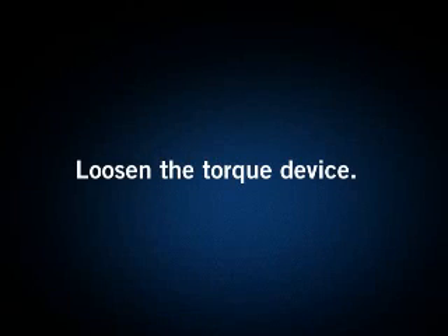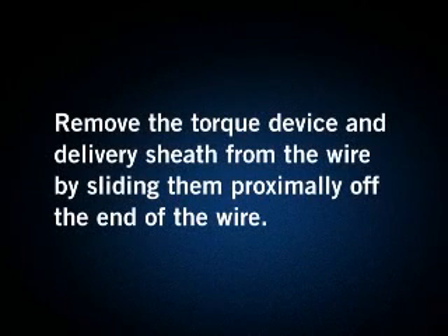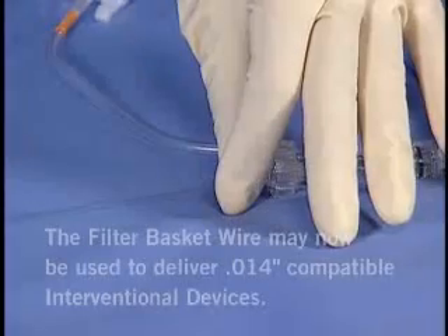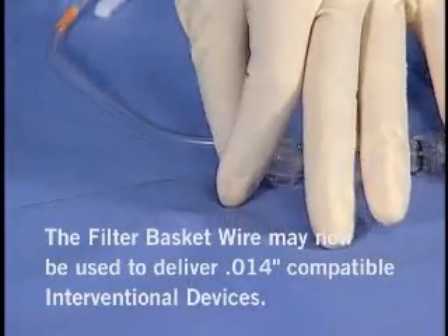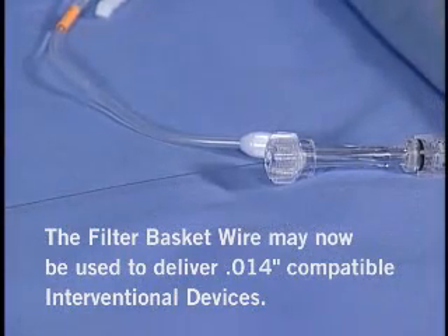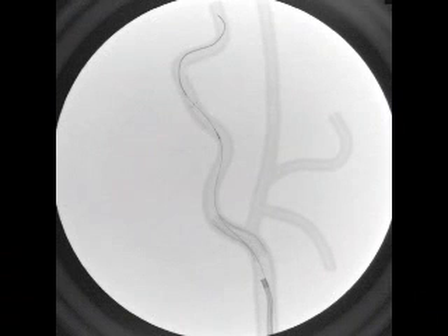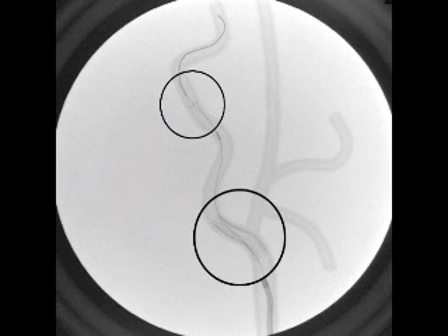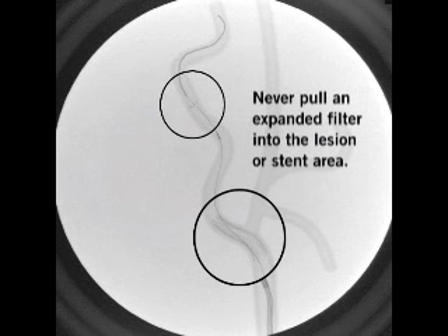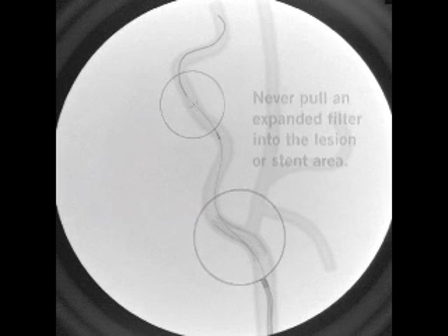Loosen the torque device. Remove the torque device and delivery sheath from the wire by sliding them proximally off the end of the wire. The filter basket wire may now be used to deliver 14/1000ths of an inch compatible interventional devices. During subsequent balloon and stent manipulations, always keep the open filter basket distal to the deployed stent. Never pull an expanded filter into the lesion or stent area.